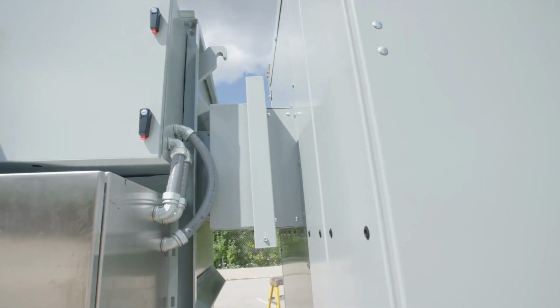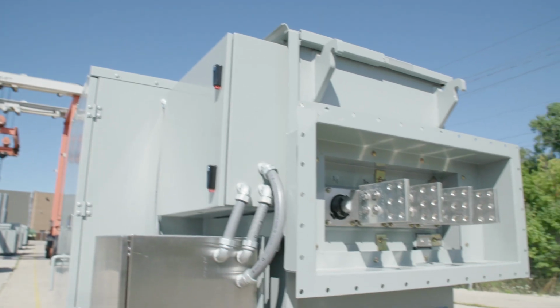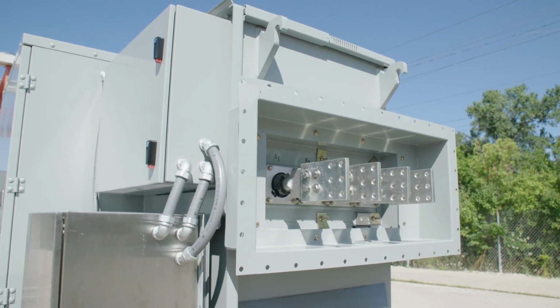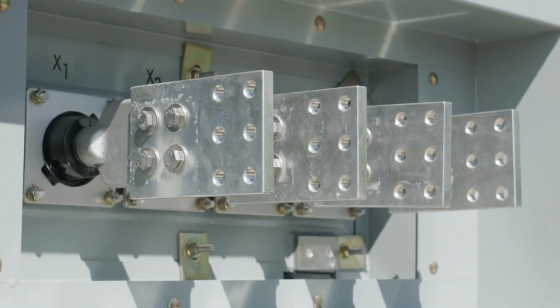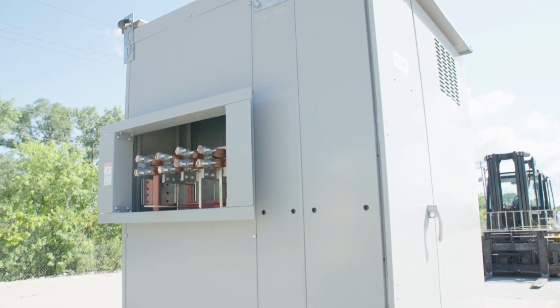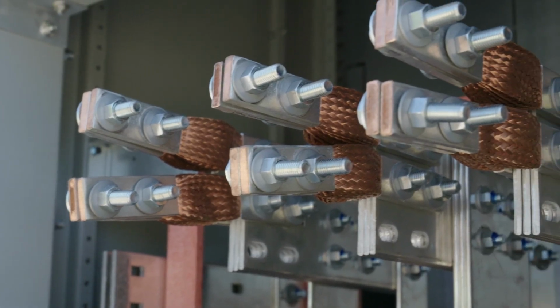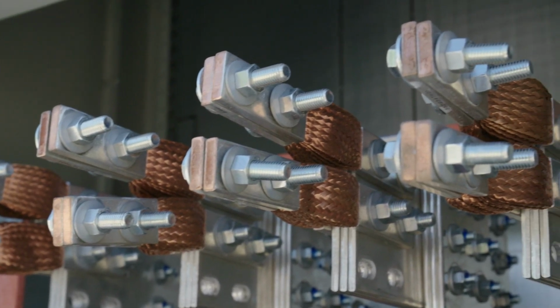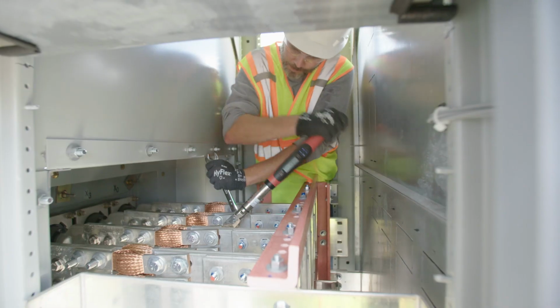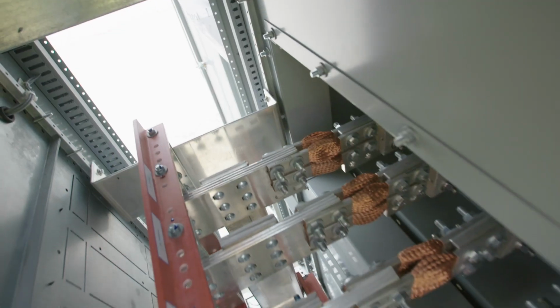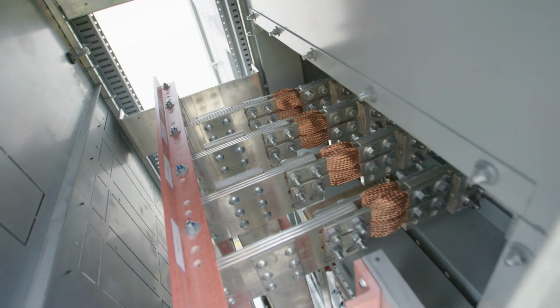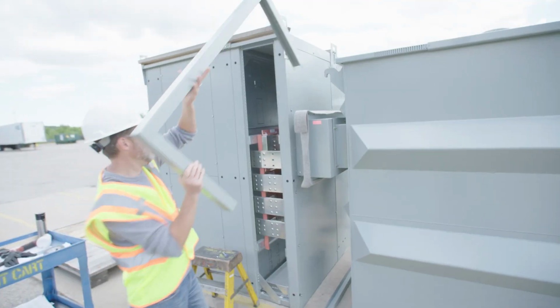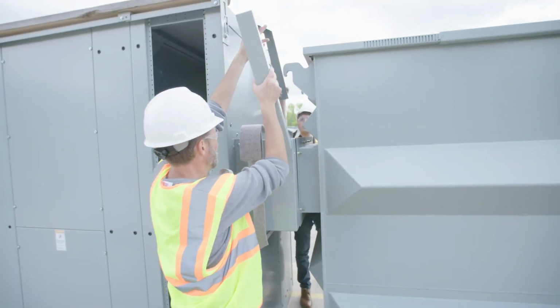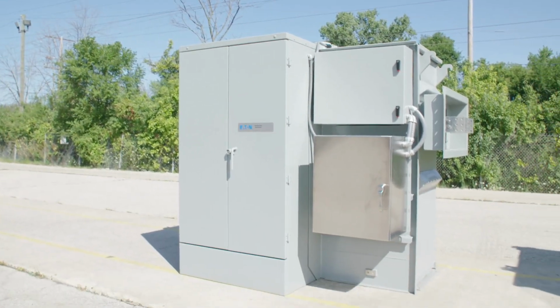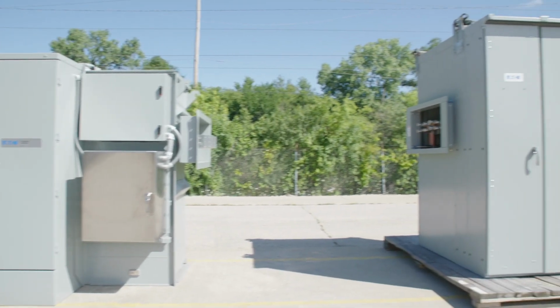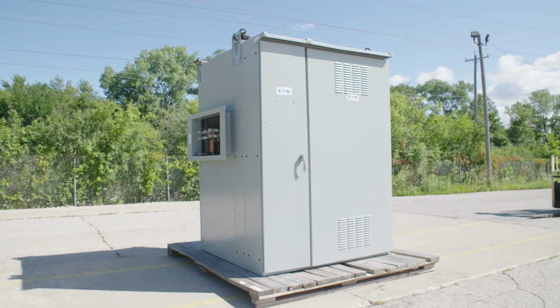As opposed to a separate AC panel and transformer, which are not necessarily made for each other, the close-coupled connection of Eaton's solar AC collection system makes for a quick and easy installation in the field compared to an underground cable connection. Here, we'll walk you through a series of easy steps to install Eaton's close-coupled, low-voltage throat connection between a typical 2500 kVA pad-mounted transformer and a low-voltage AC recombiner switchboard.